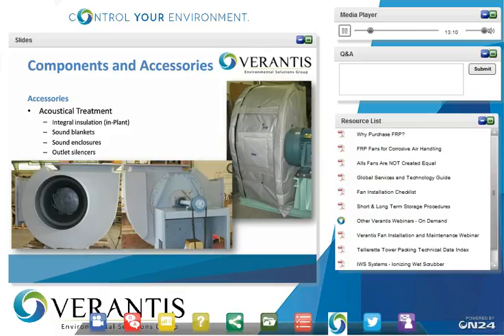A lot of times it will be called out in wastewater treatment jobs. The sound enclosure will cover the whole piece of the fan housing, base, and the motor. It is very useful if you want to control the sound level overall. The last option that I showed over here is the outlet silencer. It will only reduce the sound power along the duct stream. So you wouldn't actually be able to reduce the fan sound itself from the sound source.